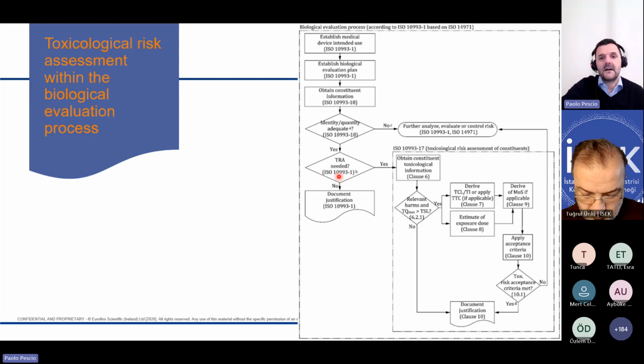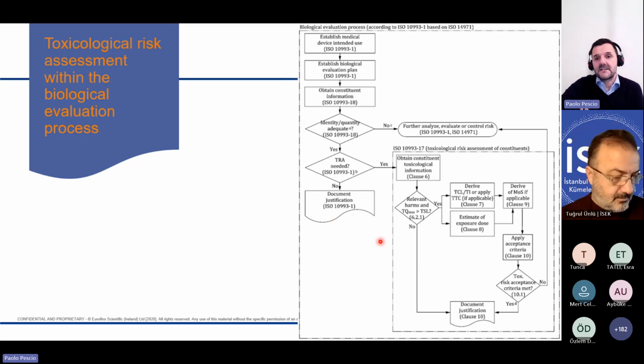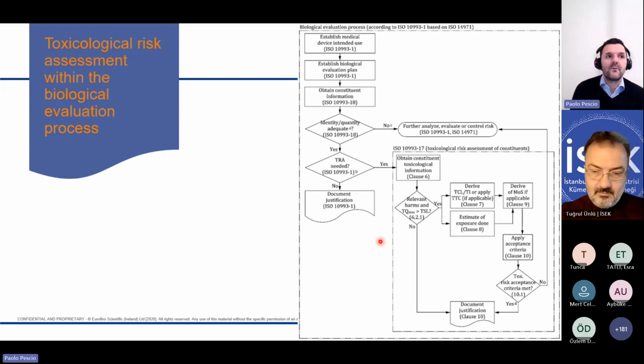In case we say that toxicological risk assessment is needed, we can use indeed the part 17 to perform the toxicological risk assessment of the constituent. We can even think that toxicological risk assessment is not needed. There are few cases, for example, devices made of very well-known materials coming in contact, for example, with intact skin. We have a quite nice list of materials that doesn't require additional information to perform the entire biological evaluation, so there is no need to perform a specific toxicological risk assessment. We justify it. Probably we have already put it in the biological evaluation plan.